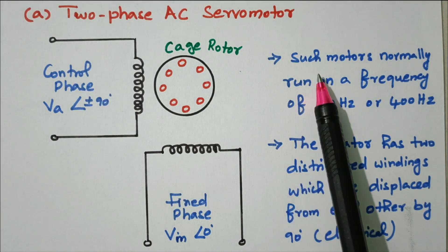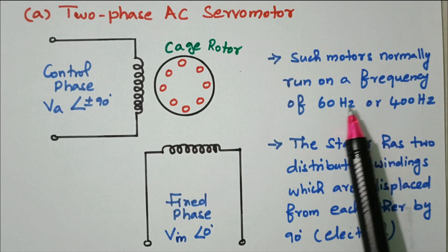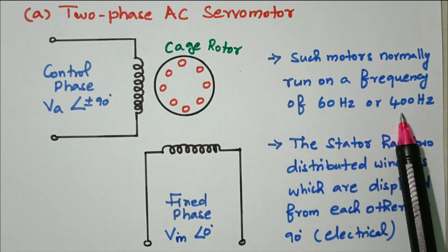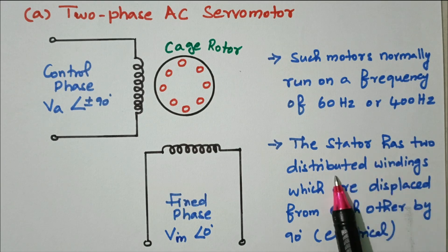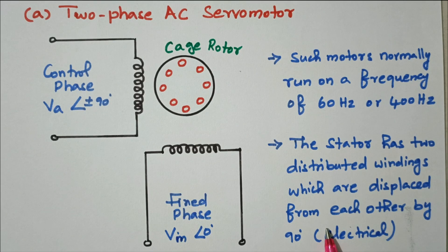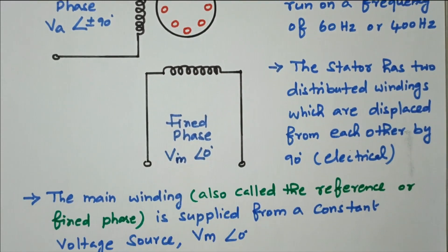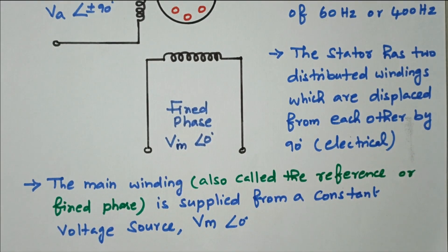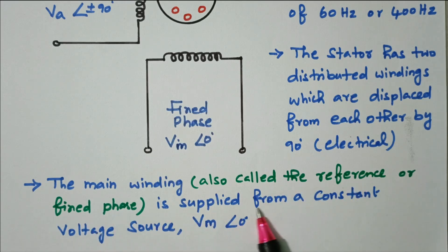The important condition is that the phase difference between the two phases — fixed phase and control phase — must be 90 degrees, then only we can use it for position control. Such a motor normally runs on a frequency of 60 Hz or 400 Hz. The stator has two distributed windings displaced from each other by 90 degrees. At 90 degrees there is no rotation; one winding is opposing the other, so any changes are reflected as speed control or position control — which is our requirement, as we do not need continuous rotation.